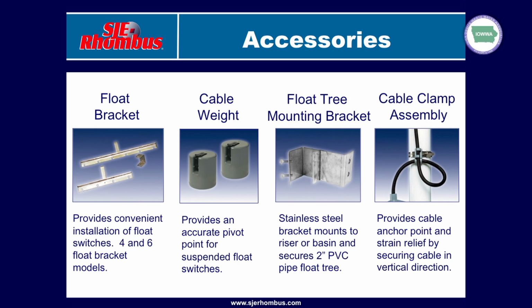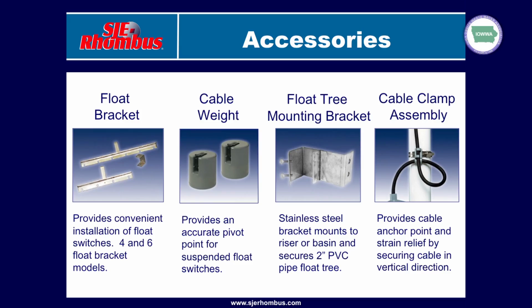Some of the different installation techniques you can use when installing a control panel with your pump, with your floats. Just a few examples, different methods for mounting the floats in the tank. We can go with a float bracket where you're going to hang the floats from the top of the tank. Typically this float bracket would be installed in the riser in the top, and then you would hang floats from each of those little positions there. If you're using a float bracket to hang the floats down into the tank, you're going to control the activation point by the length of cord that you have coming down into the tank, and your tether point is going to be controlled with a cable weight that's going to attach to the switch cable with our 3.5 inches minimum length of tether. And there's a picture of a cable weight.